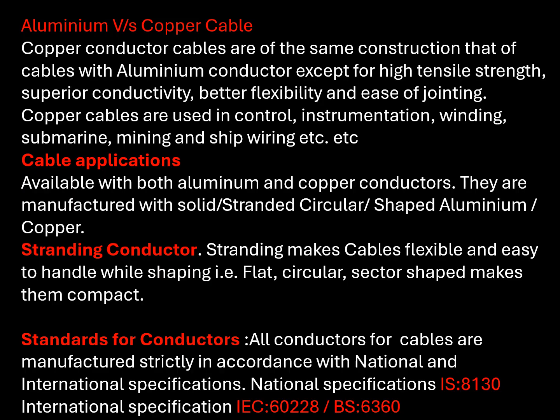Standards for conductor. All conductors for cable are manufactured strictly in accordance with the national and international specifications. National specifications such as Indian Standard 8130 and International Specification IEC 60228 or BS 6360. Friends, we are talking conductors here, not cables.